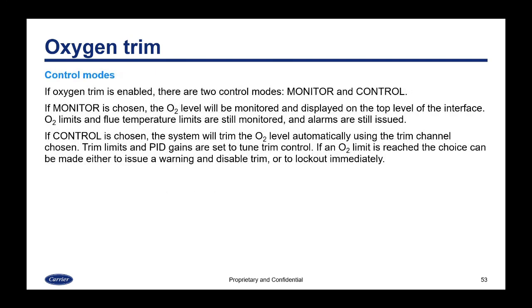If oxygen trim is enabled, there are 2 control modes, monitor and control. If monitor is chosen, the O2 level will be monitored and displayed on the top level of the interface. O2 limits and flue temperature limits are still monitored, and alarms can still be issued based on those limits. If control is chosen, the system will actually trim the O2 level automatically using the trim channel chosen, and that would be air or fuel. Trim limits and PID gains are set to tune trim control. If an O2 limit is reached, the choice can be made to either issue a warning and disable trim or to lock out.